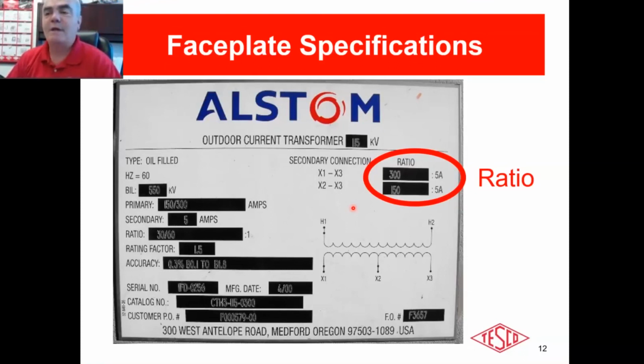But if you have these out on your system, I guarantee you that somewhere on your system, there's a place where billing thinks you hooked up the 300 to 5, and it's really hooked up as a 150 to 5. And the opposite is true, where billing thinks it's a 150 and it's actually a 300. So think about that. In the one case where billing thinks it's a 150 and you hooked it up as a 300, we're billing the customer 50% of their usage. If you flipped it around and billing thinks it's a 300, but you hooked it up as a 150, we're billing the customer double what they should be billed. Neither one is a good thing. Both end up very ugly with very upset customers.